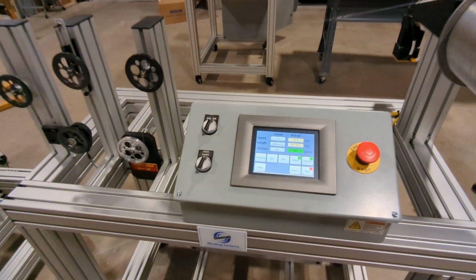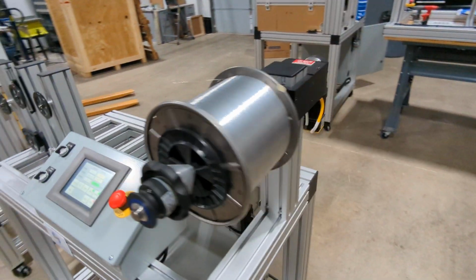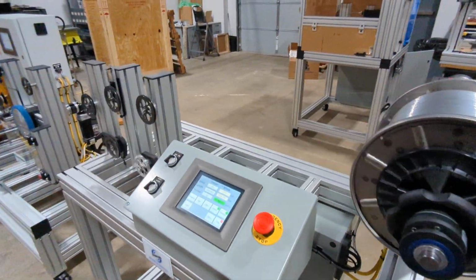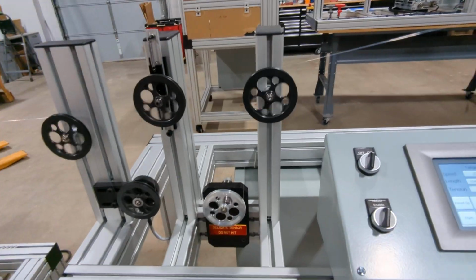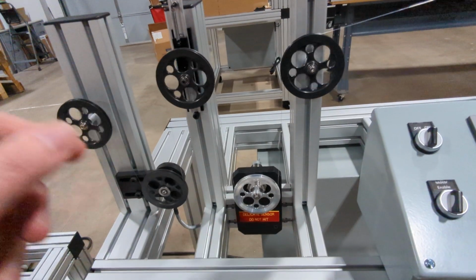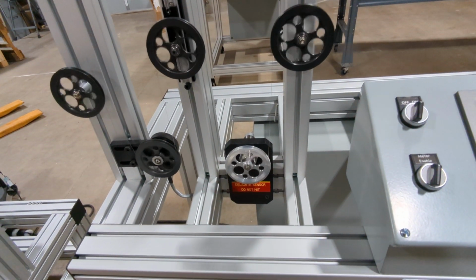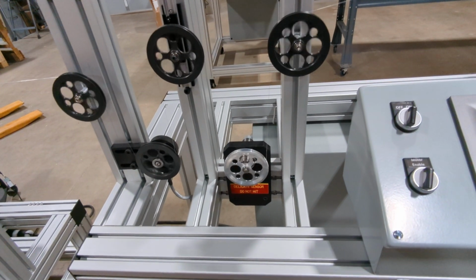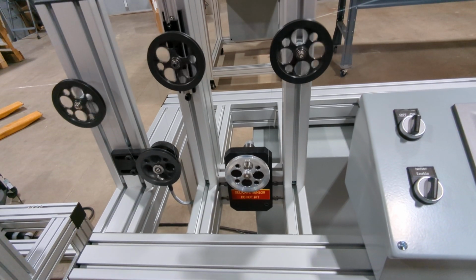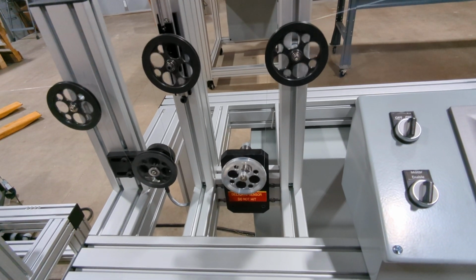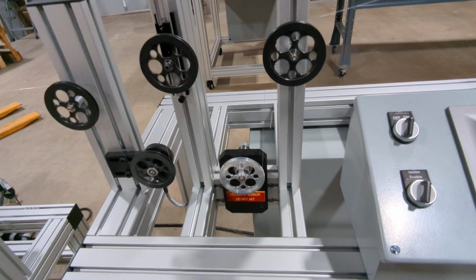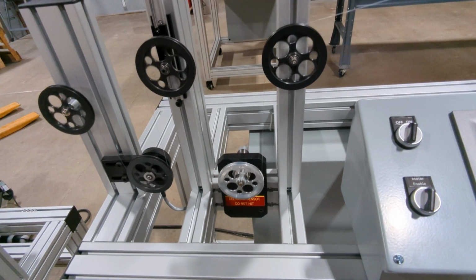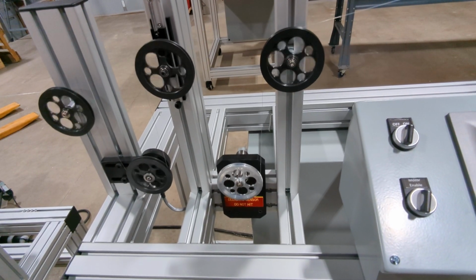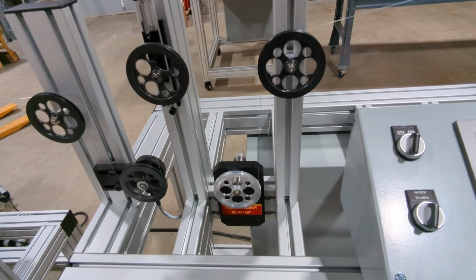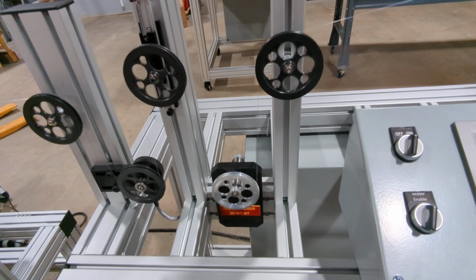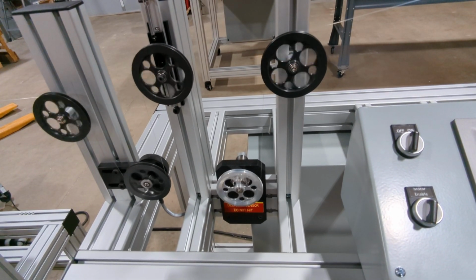If you look a little closer here on the machine, it's got a servo on the payoff. The wire is being fed down to a tension transducer. In this case, we're using a solid state transducer with a range up to about 500 grams. And that's just one of a few different tension solutions we have. We also have a couple dancers for much lower or higher tension depending on the requirement. We can get down to about 5 grams with these machines.